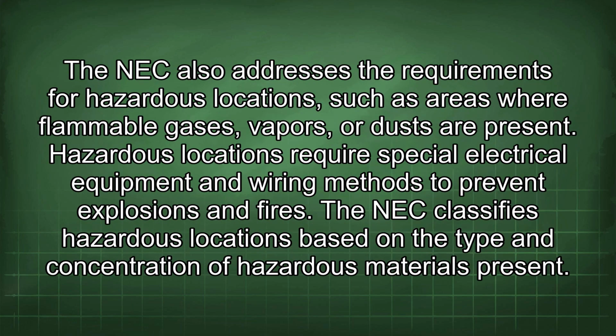The NEC also addresses the requirements for hazardous locations, such as areas where flammable gases, vapors, or dusts are present. Hazardous locations require special electrical equipment and wiring methods to prevent explosions and fires. The NEC classifies hazardous locations based on the type and concentration of hazardous materials present.